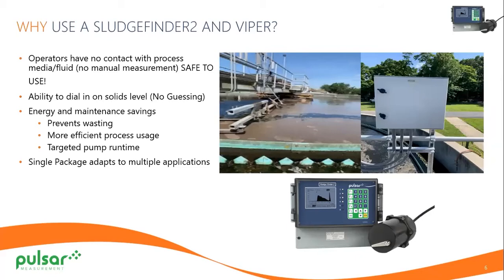Why use a Sludge Finder 2 and Viper? One of the biggest reasons is money savings. You want to be able to have that process be efficient. You really don't want wasting. You can set your pumps to run to a certain level and turn them off. Another huge key to the Sludge Finder 2 and Viper is the fact that you do not have to use a manual tube to take the measurement. With COVID now being in wastewater, there's an opportunity that you may touch that COVID.